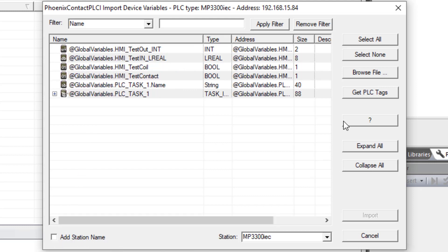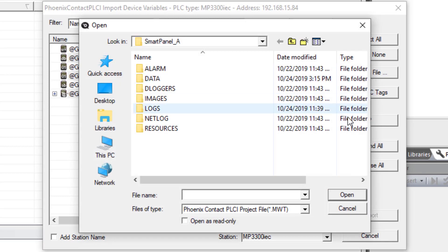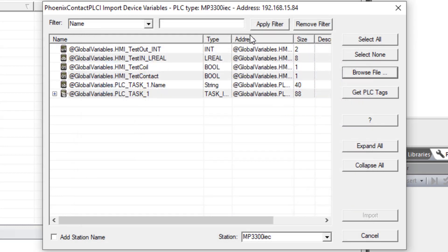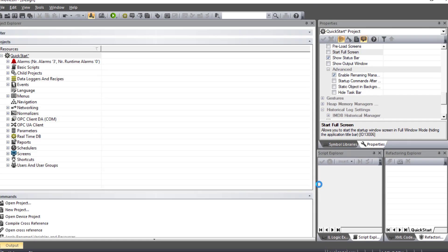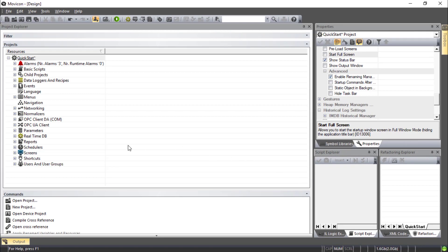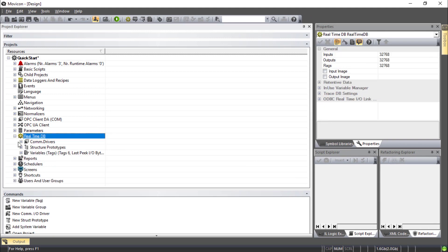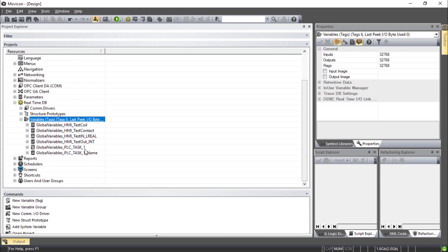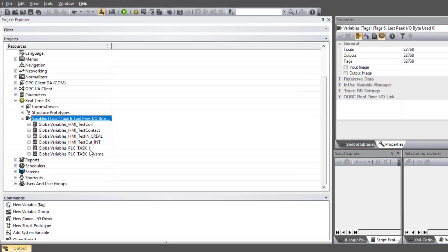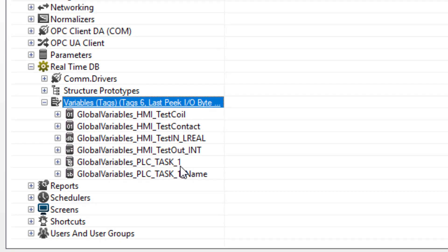And now if you're not connected to the controller, you could still browse to find the MWT file for your project and import the variables from there directly. Now select all the variables you want. I'll do select all and import. You can find the variables in Movicon under real-time DB variables. There they are.